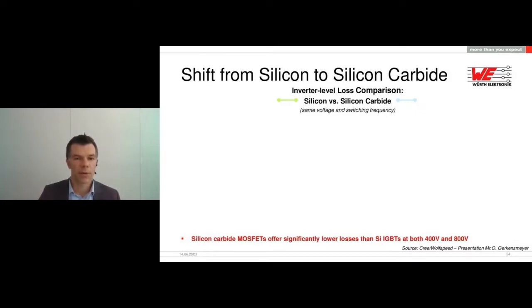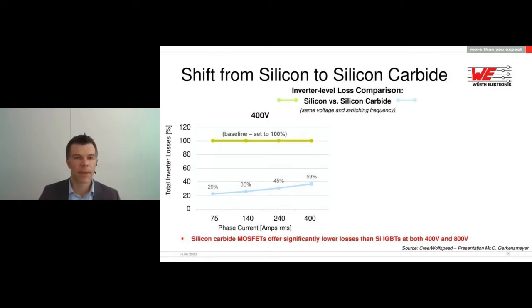If you compare here on a 400-volt system the total inverter losses, taking the baseline on the left side, the green baseline of 100% as the silicon regular device as you might know it since years, and compare that to silicon carbide with a certain switching frequency, you can see the losses drop significantly. We end up at 29%, or at 400 amps, even still at about 50%.